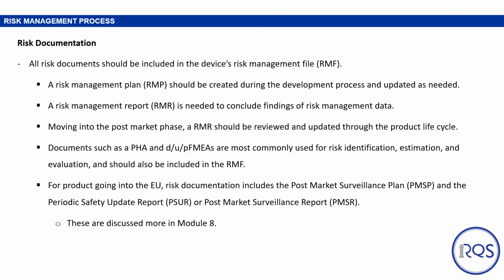This should be created during the developmental process and should be updated as needed. We also have a risk management report, or RMR, and that is needed to conclude the findings of risk management data. And then moving into the post-market phase, the RMR should be reviewed and updated throughout the product's life cycle.